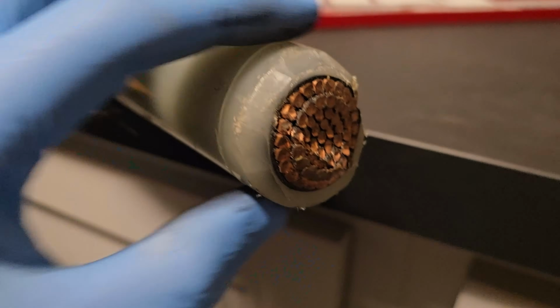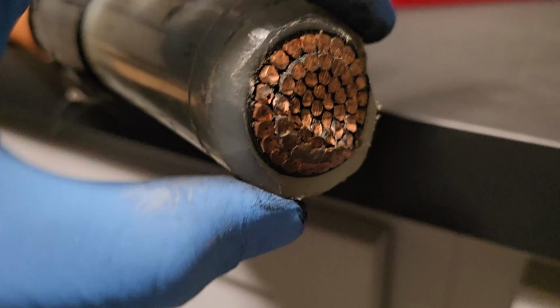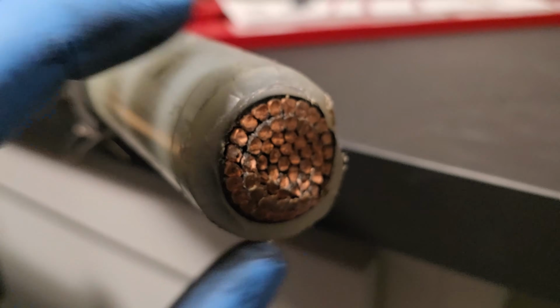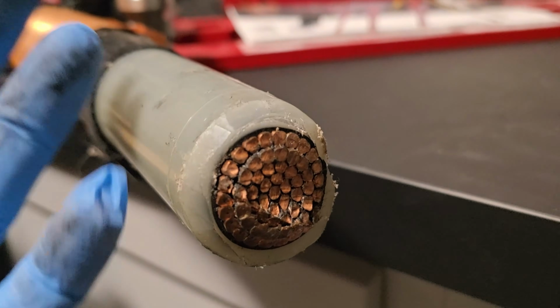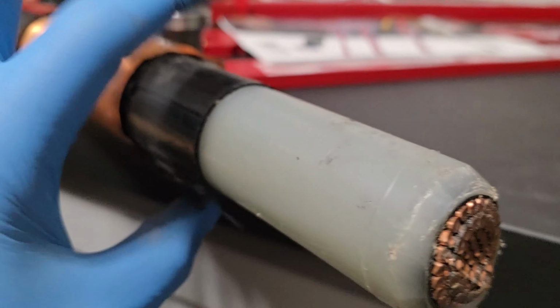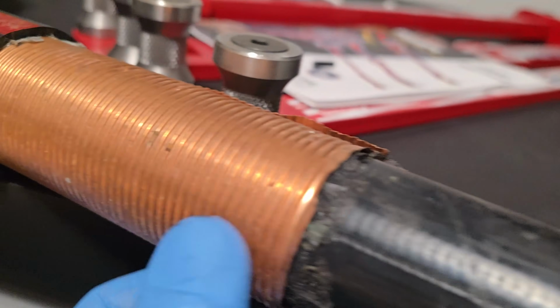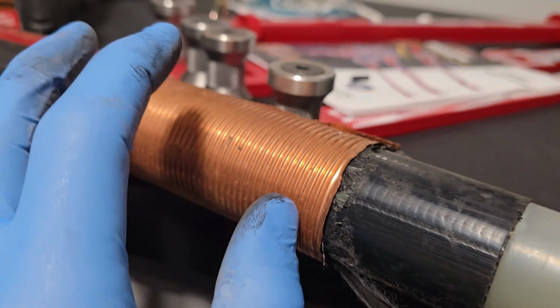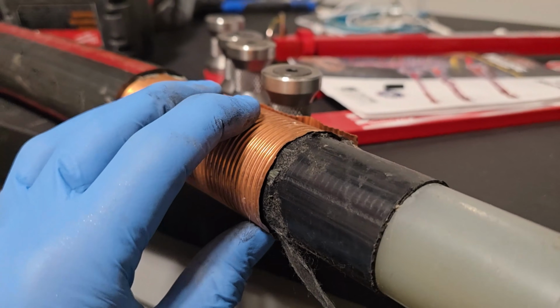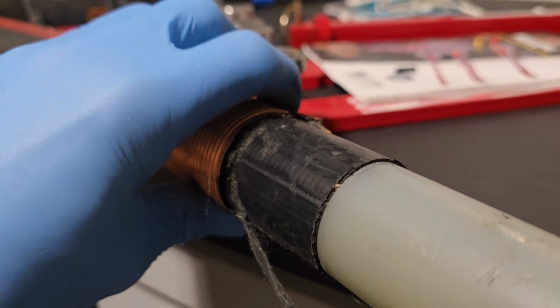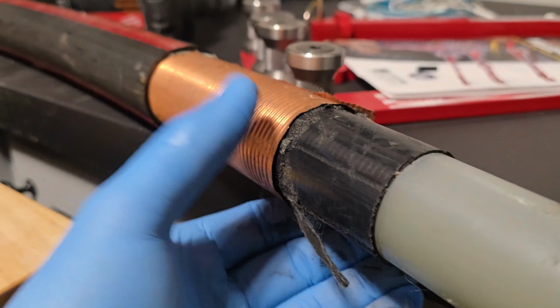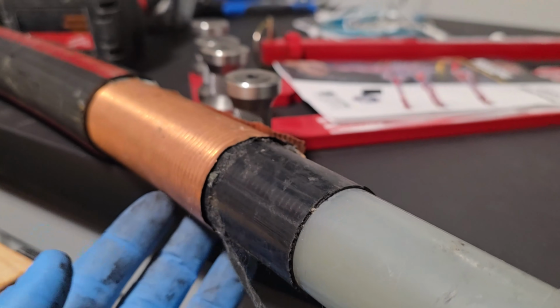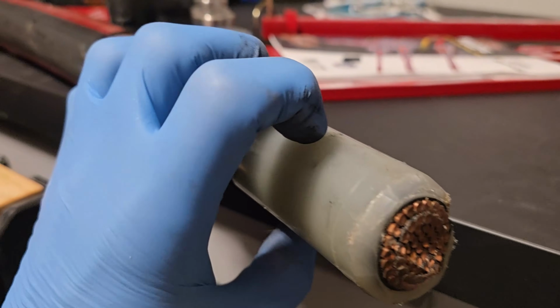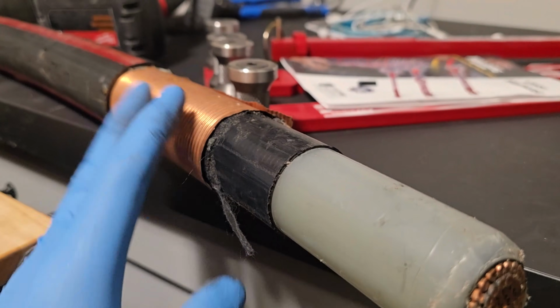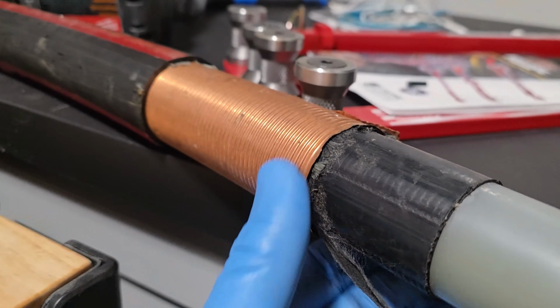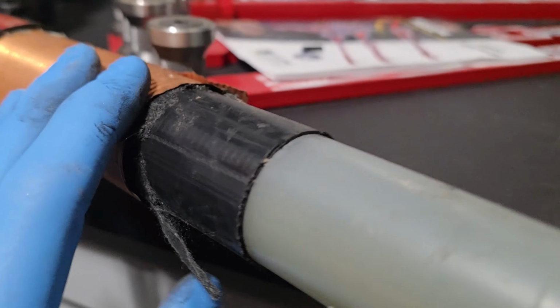You have your layer of insulation. This is ultimately what's keeping the voltage from escaping, for lack of better words. Then we have semicon, and then we've got our ground. Some cables have a concentric neutral, some have a jacket shielding. This can be tapped off of and used as a neutral, or in this case, where this was a feeder cable, that's just grounded on one end, just for shielding, but there was a separate neutral run.